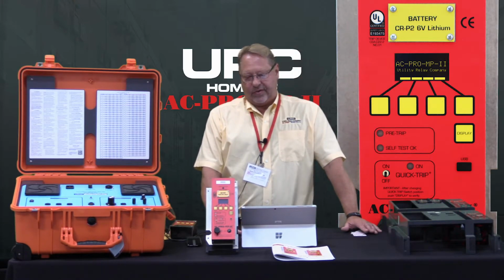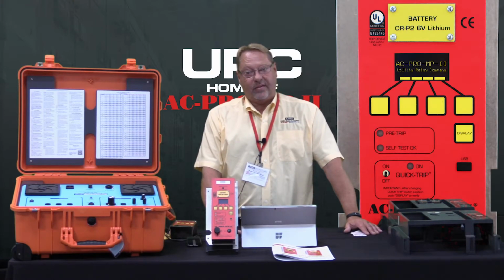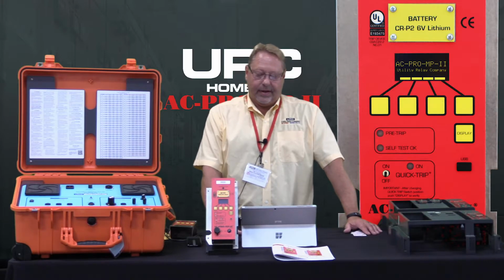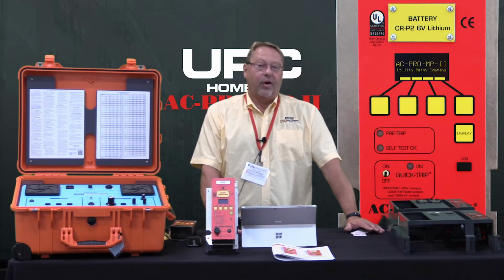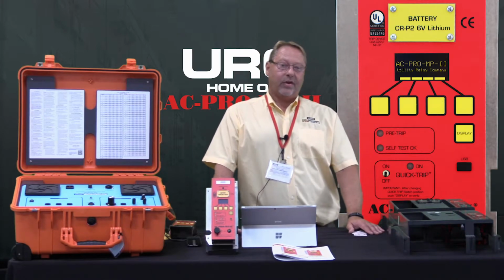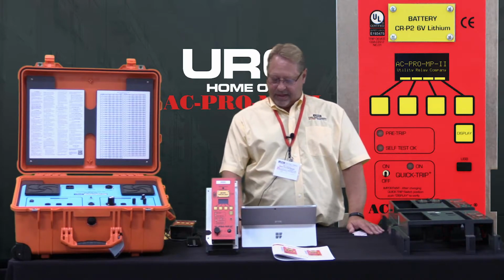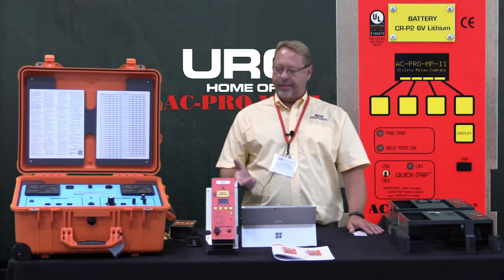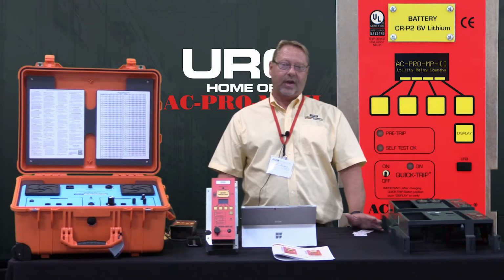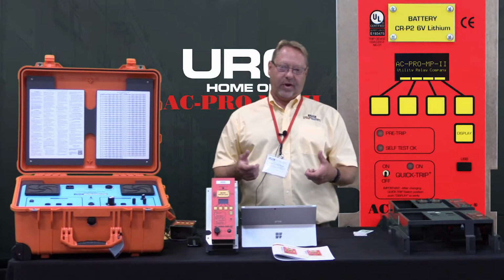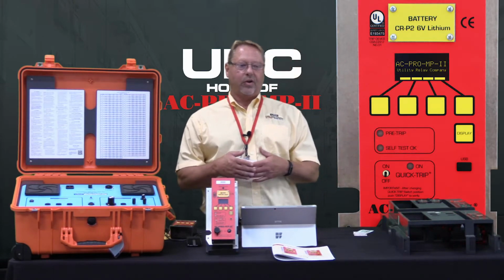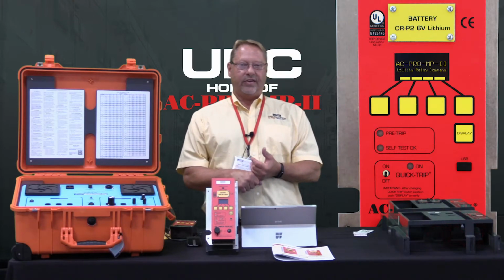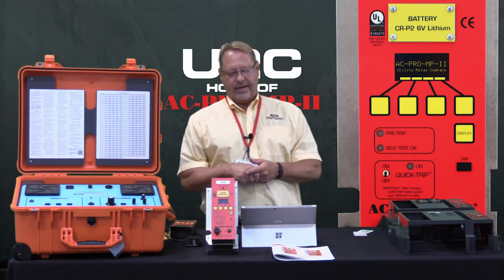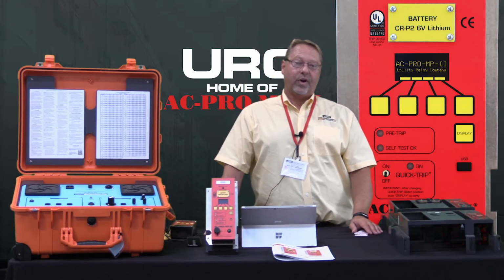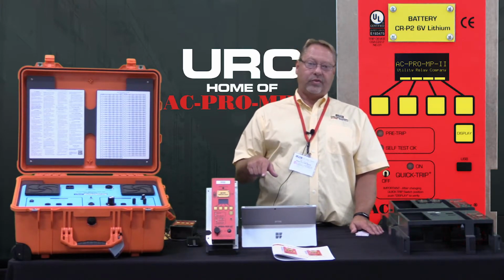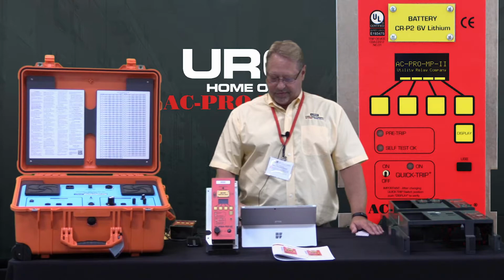It's a worldwide breaker, so when we did the development, we did it for both 50 and 60 hertz markets. Most of the units sold abroad are all 50 hertz. US and some other countries are 60 hertz. It was the first breaker in the world, for that matter, that started measuring the mechanism time of the breaker. We're starting to monitor the speed of the breaker. And monitoring speed is important because if the breaker opens up too slow, then your coordination studies don't work, your arc flash boundaries get large. So it's a patented solution that we call sluggish breaker detection. This product, along with the AC Pro 2, both have those very important features as well.